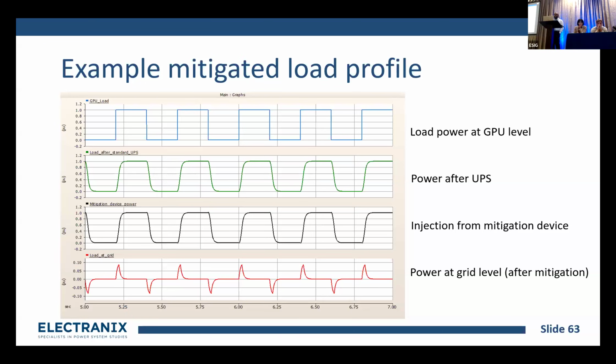The one at the bottom is essentially the second one minus the third one. So the gap between those two is the red one. For the red one, you can see the peak to peak, there is a value left. This is the value that the grid requirement is looking at. This value needs to be lower than a certain value, the peak-to-peak number, let's say 10 megawatt, 20 megawatt. So that's a very important number to look at. Let's go to my final slide.